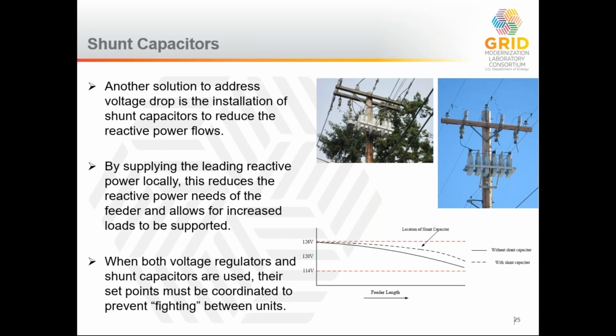Here below, we see another example of the type of curve that you can have. Basically, the shunt capacitor just moves up the entire thing a little bit. Now, shunt capacitors can be put in different ways. They can either be fused directly into the system, so if you expect there's always a need for reactive power, they can do that. But they can also be put in with switches so that they can be turned on and off at different times.